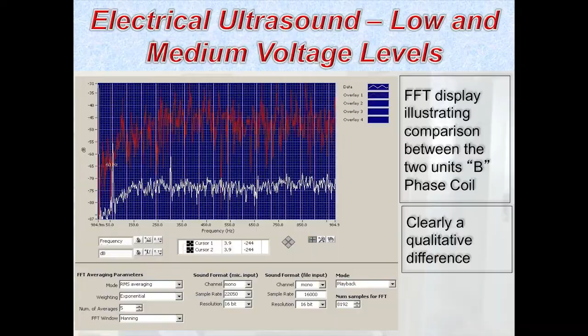Because there's a right way and a wrong way to use the spectralizer for electrical applications. Up here, we know there's a qualitative difference in the sound of the recordings, but this is looking at the frequency spectrum for both B-phase coils on the suspect unit and the good unit. In general terms, does there appear to be a difference? What can you pick out from there that stands out? The amplitude of where the harmonic frequencies are and the amount of noise in between each one of those.